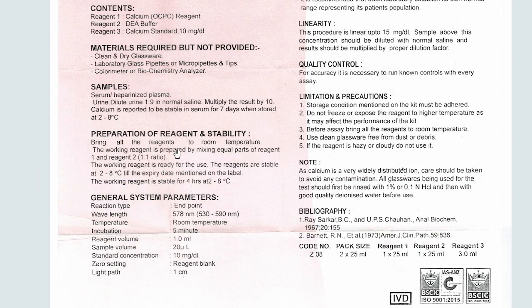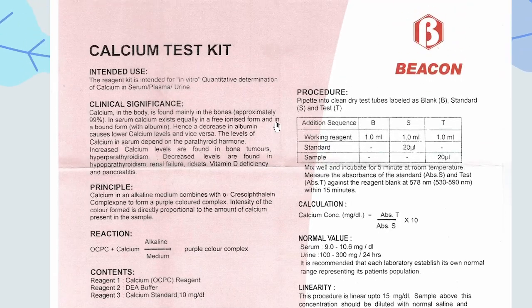So general system parameters, of course, this is an endpoint na assay or reaction since wala tayong specific na time nag-i-allot. And then you have your wavelength, and then incubation time is 5 minutes. Your reagent volume is 1. Your sample volume is 20 microliter. And then, against reagent blank po itong OCPC test nyo.